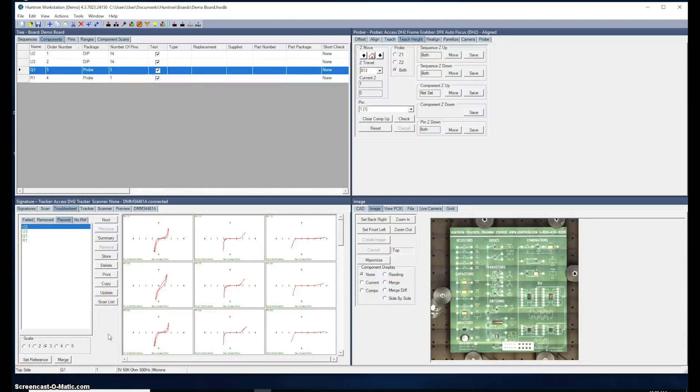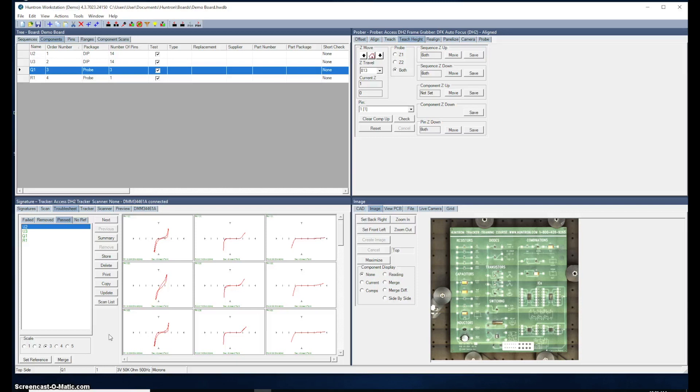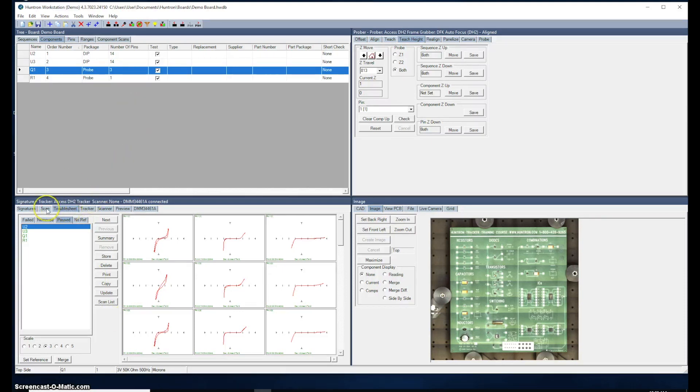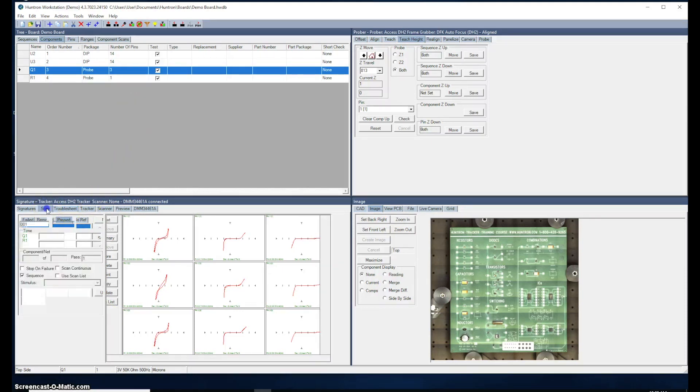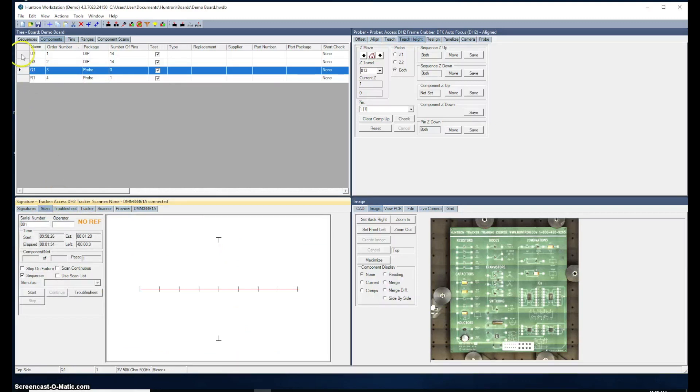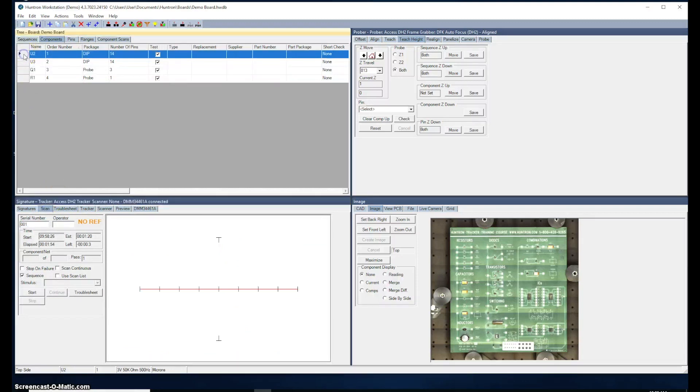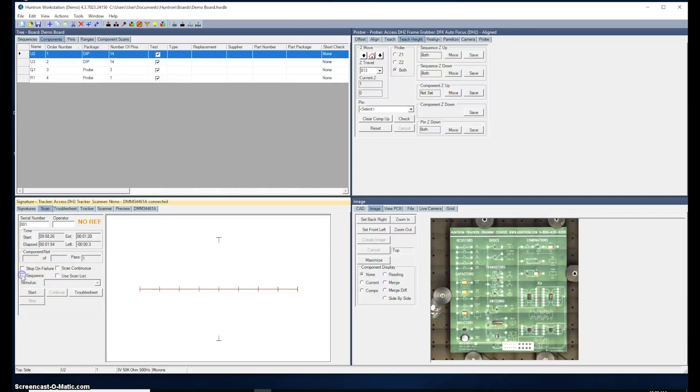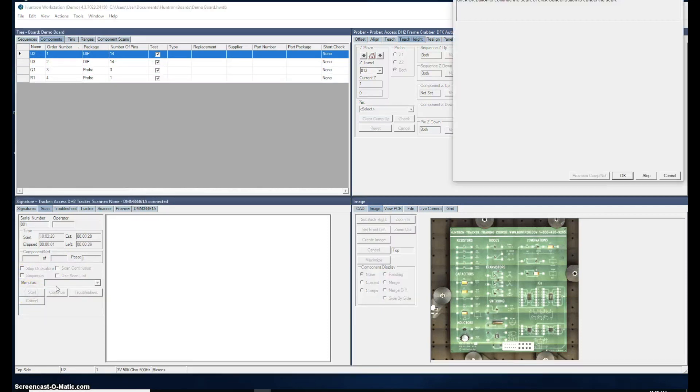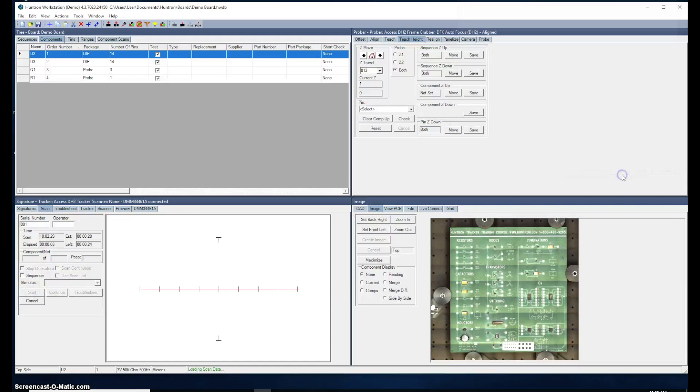Now the idea would be to put another board in here, a bad one, and scan that and it will come up with the differences between the two boards. I'm going to simulate a difference by putting a fault on the board and then run the scan again. Just for the benefit of saving some time, I'm only going to scan one component. I happen to put a fault here on U2. So we'll just scan U2 only. We'll uncheck the sequence check box, click start, and click OK. Now the probe is only going to go over and scan U2. You can see the signatures being captured.